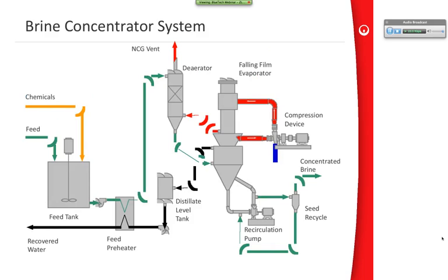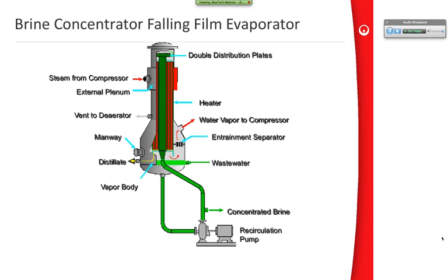This is a so-called brine concentrator system. It consists of the basic evaporator, but it has a couple of components. Besides that, there's a tank to add some chemicals, to adjust the pH, and to make sure that we have all of the components necessary to remove any dissolved gases, which is done in the deaerator. There's usually a compression device, a compressor, because these are typically MVR systems or mechanical vapor recompression systems. And then there's a seeding system or a seed recycle system, which we'll talk about in a minute, to help us control scaling in this brine concentrator system.